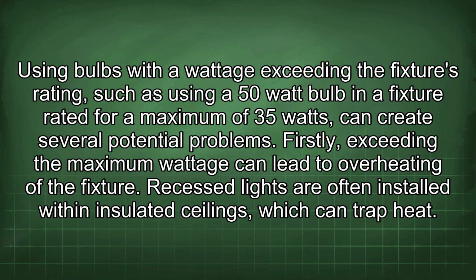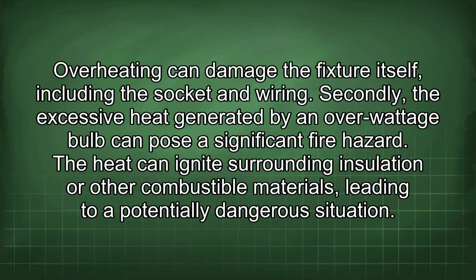Firstly, exceeding the maximum wattage can lead to overheating of the fixture. Recessed lights are often installed within insulated ceilings, which can trap heat. Overheating can damage the fixture itself, including the socket and wiring. Secondly, the excessive heat generated by an over-wattage bulb can pose a significant fire hazard. The heat can ignite surrounding insulation or other combustible materials, leading to a potentially dangerous situation.